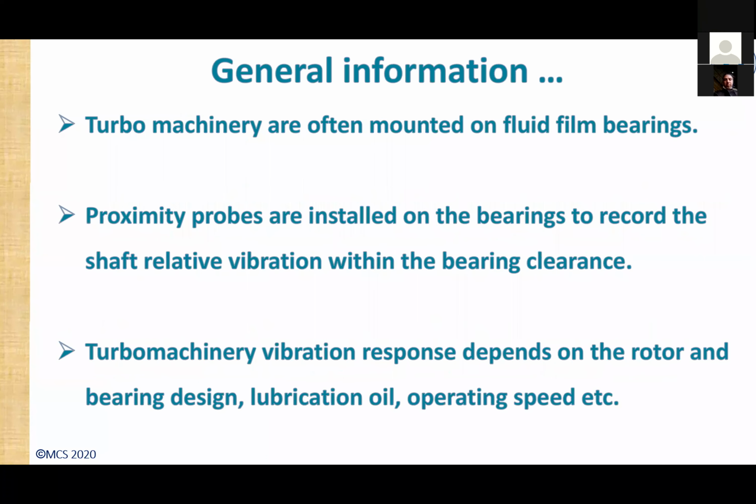The general information: turbo machinery are often mounted on fluid film bearings. Proximity probes are installed on the bearings to record the shaft relative vibration within the bearing clearance. And the turbo machinery vibration-based response fundamentally depends on the rotor, the bearing design, lubrication oil, the operating speed, and some other parameters as such.